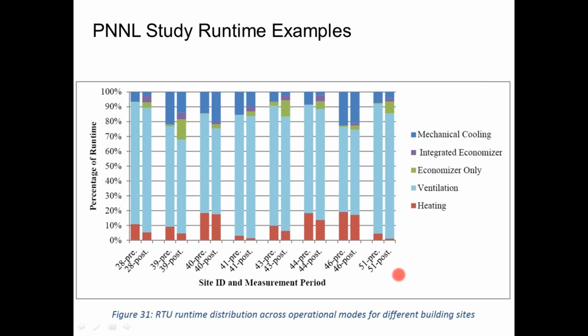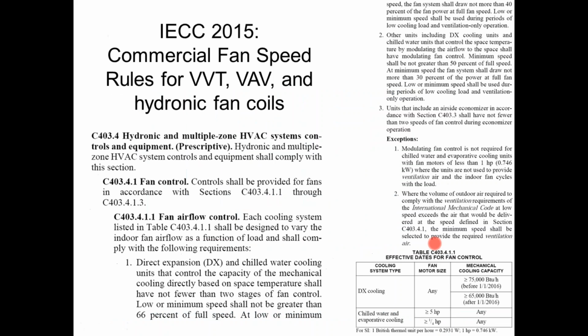So we can somehow magically make your rooftop unit go from 80 to 83% thermal efficiency on the heat side. Whoopee, right? We can make you do 14 IEER someday on the cooling. Whoopee, right? The fan is what's using all the energy. The fan is the dominant operating energy source here. As you probably noticed in other aspects of the code, the fans have been getting picked on. By picked on, I mean they've been requiring more efficiency, in different ways. So here's one of those ways that comes up.